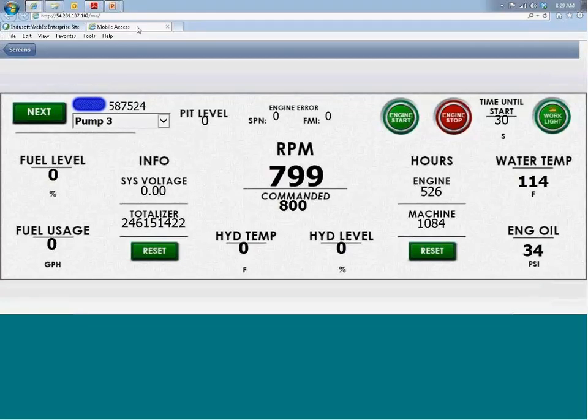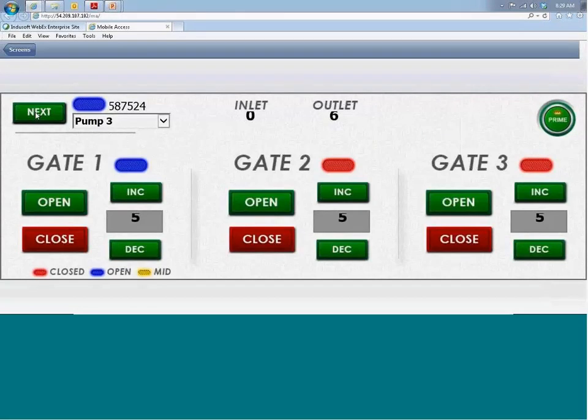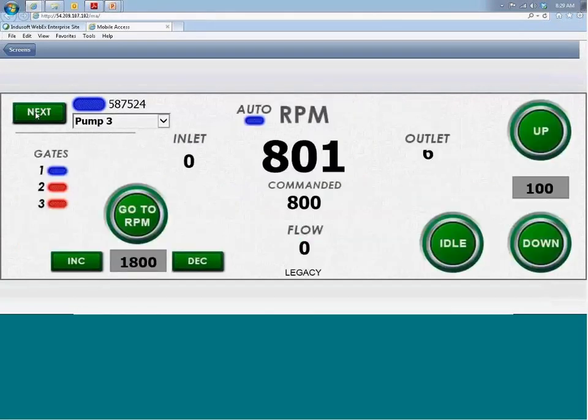This is a subscription model, so there is no polling from the browser to the server. The browser shows the graphical screen, and as values change on the server, the server itself automatically pushes updated values to the thin clients, to the browsers, and the browsers automatically update the information on the browser.